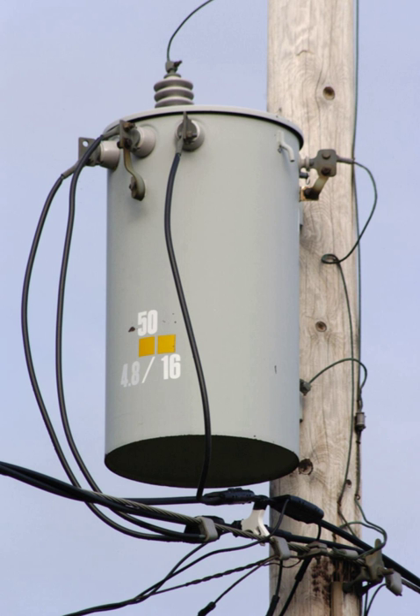Primary distribution. Primary distribution voltages range from 4 kV to 35 kV phase to phase, 2.4 kV to 20 kV phase to neutral. Only large consumers are fed directly from distribution voltages. Most utility customers are connected to a transformer, which reduces the distribution voltage to the low voltage utilization voltage, supply voltage, or mains voltage, used by lighting and interior wiring systems.